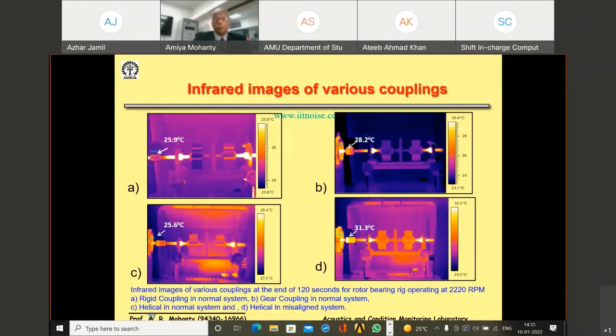And this is important because these are all rotating, so I possibly cannot put a thermocouple on a rotating device because of the cables. But if I have an infrared camera focused and shooting at that surface, I can record the temperature. This was being logged at 30 frames per second. We had to set the emissivity, and then with this software we could capture the images.